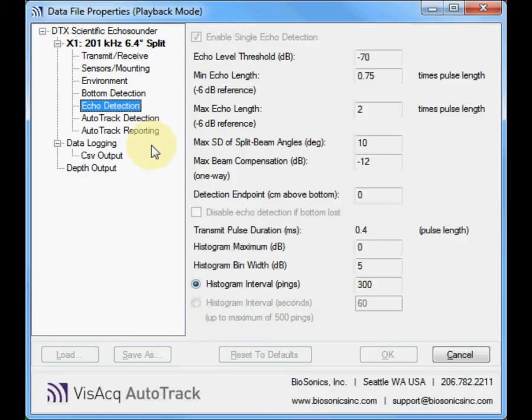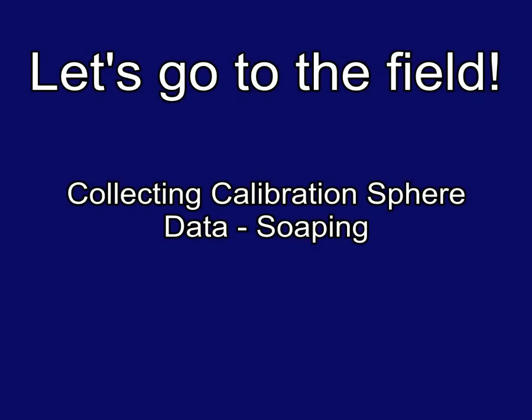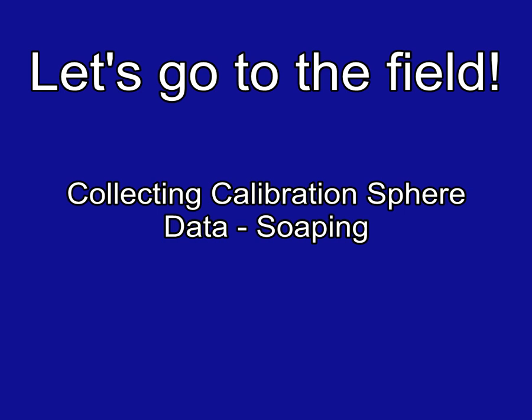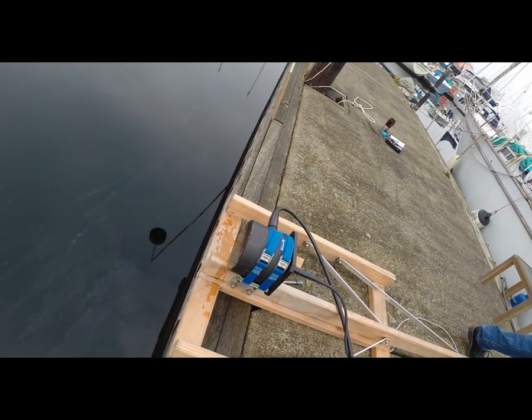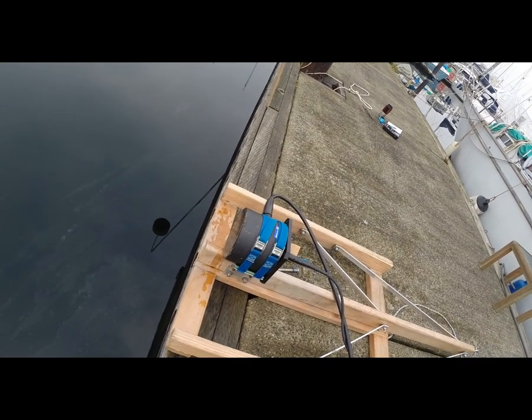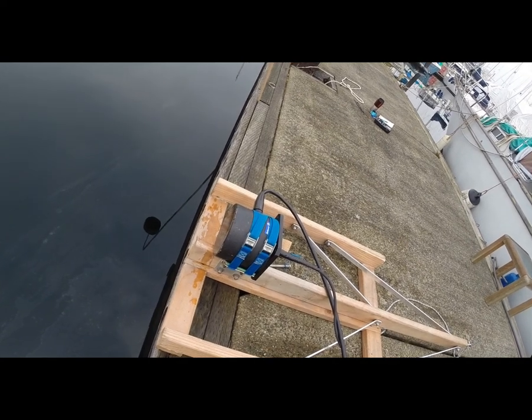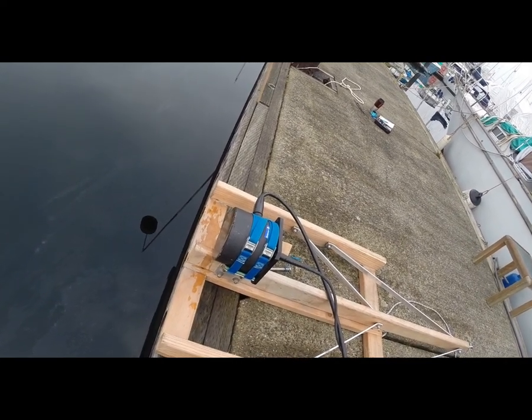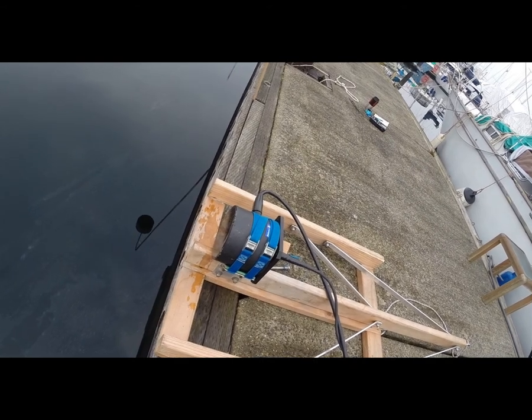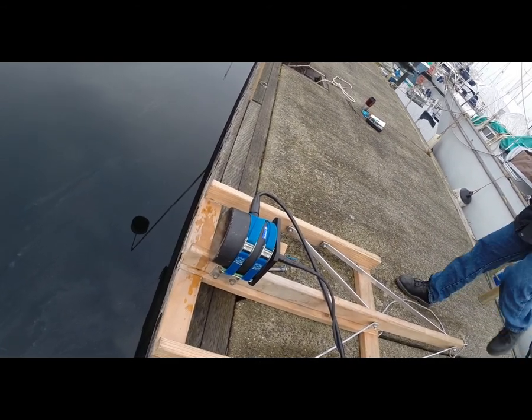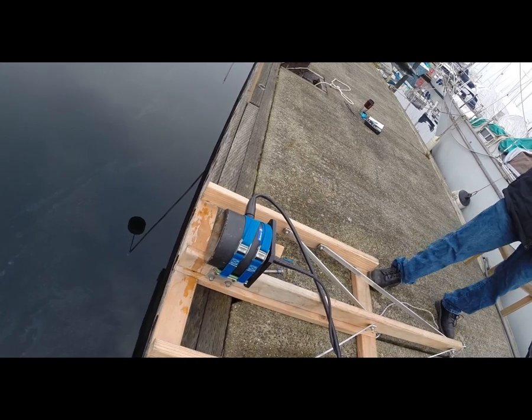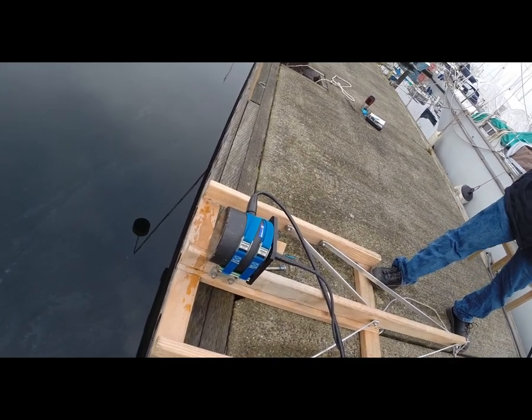Now that we've entered in our data collection parameters, we can go ahead and save this configuration to help ensure a consistent field calibration check data collection program. We apply a biodegradable no phosphorus soap to the face of the transducer, just a tiny bit to break up the surface tension so we don't get bubbles trapped on the surface when we put it into the water. Same goes for the CalSphere.